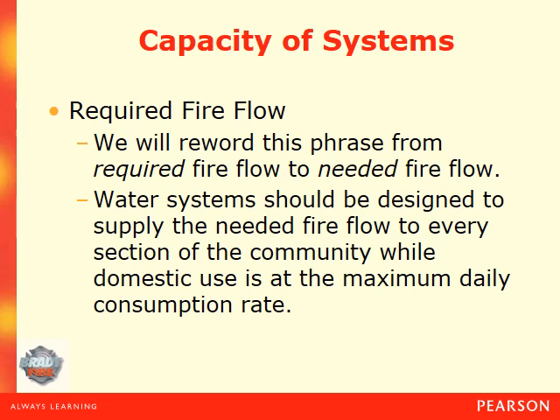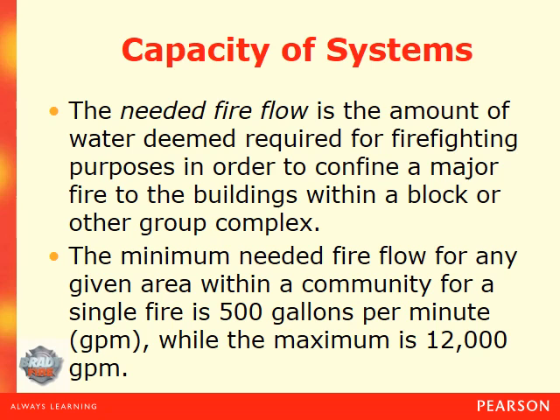Water systems should be designed to supply the needed fire flow to every section of the community while domestic use is at the maximum daily consumption rate. The needed fire flow is the amount of water deemed required for firefighting purposes in order to confine a major fire to the building within a block or group complex. The minimum needed fire flow for any given area within a community is 500 gallons per minute, while the maximum is 12,000 gallons per minute.